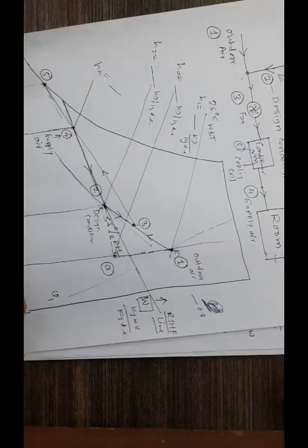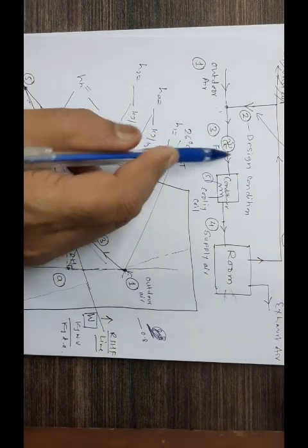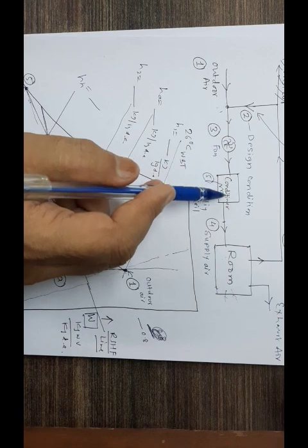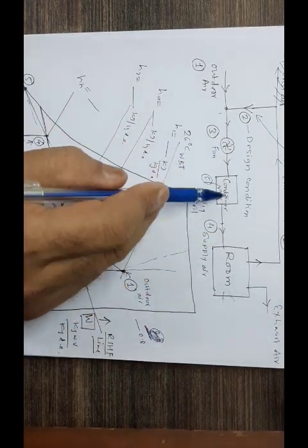However, now the fan comes into picture. You are not supposed to be taking fan additional thing here, but this fan, if it is 12 kilowatts, is going to add heat as additional load on the conditioner, not into the room. This load is not added into the room. This load is added on the conditioner.